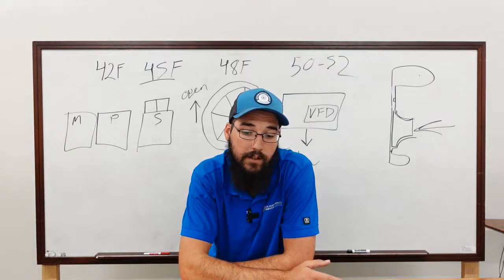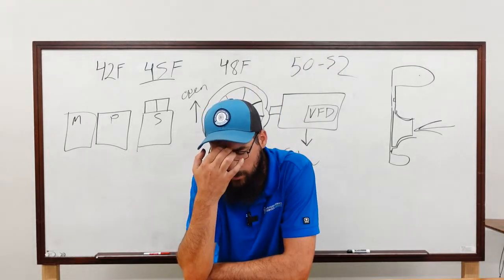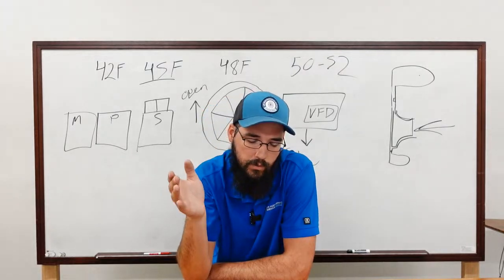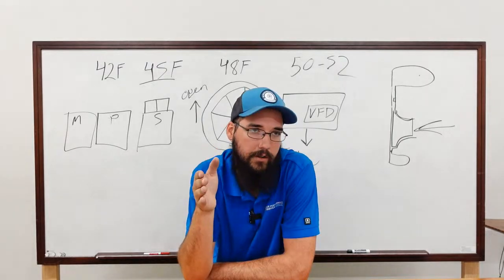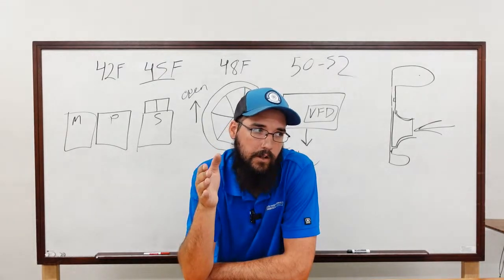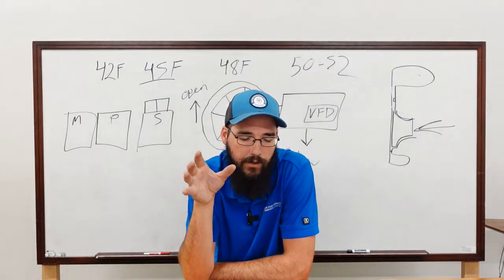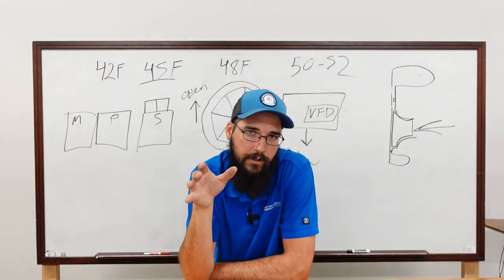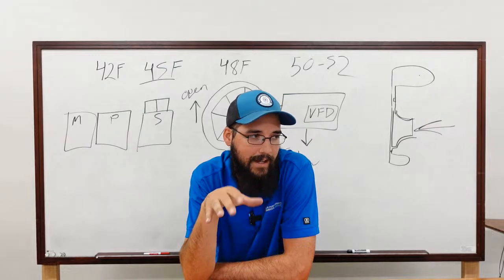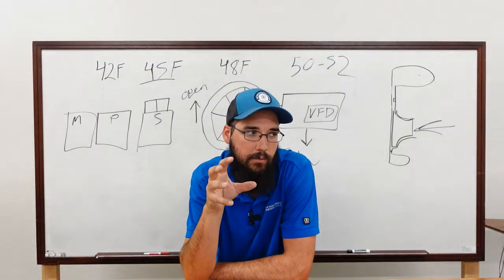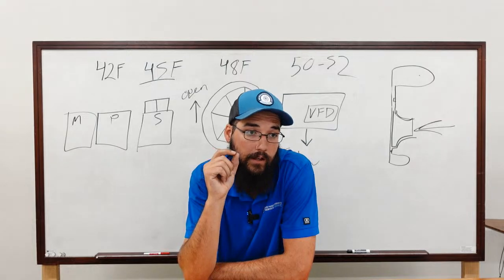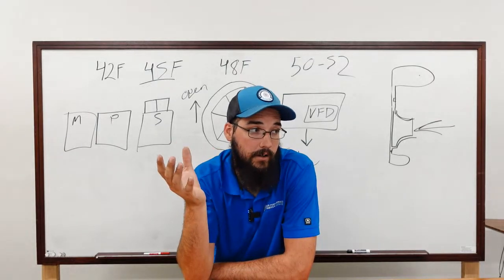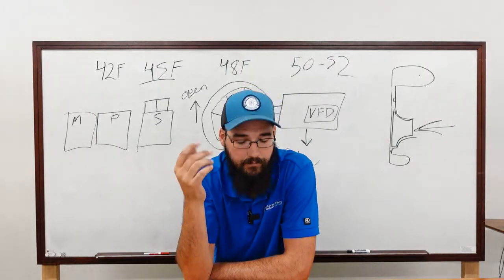And what that does, the reason the current limit helps is we're not pushing the condenser water as hard. Because we're not pushing the condenser water in terms of heat, we don't need as much cooling tower to keep the water cooler. And that's kind of the tricky point. So that's what I would do, in terms of, okay, where do I set my current limit? How high do I go with it?